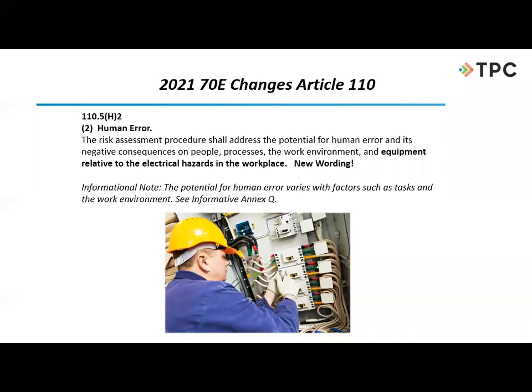On 110.5 H2, which deals with risk assessments, step 2 of the risk assessment — the first step would be identifying the hazard, and now we're into making a judgment on how likely it would be that we might get injured. They are telling us now that we have to take into consideration the electrical equipment relative to the hazards, and we have to take into consideration the person doing the work.